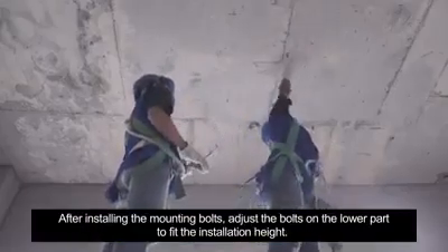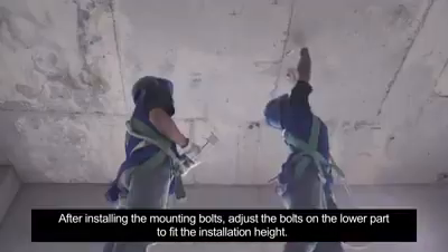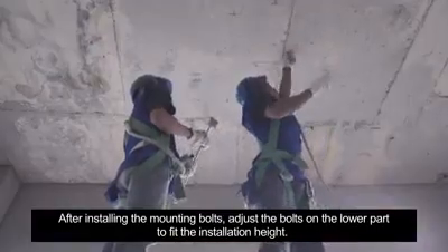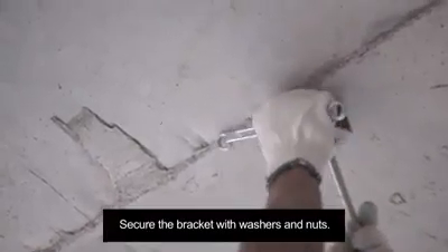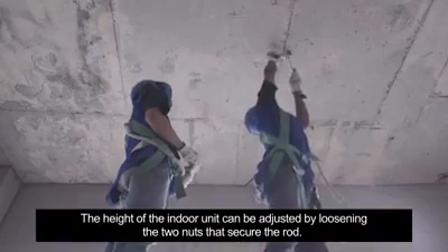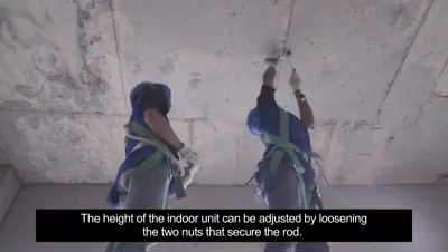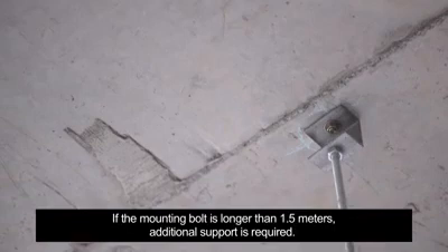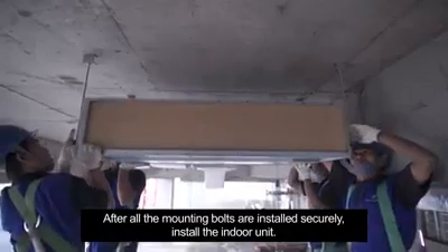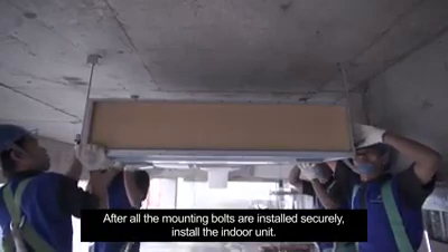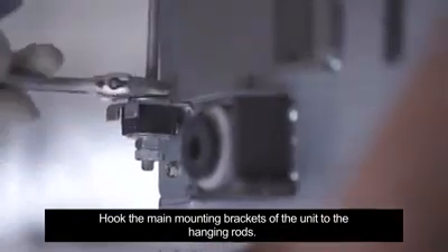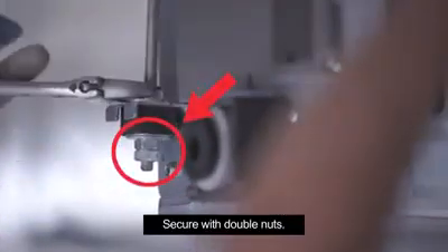After installing the mounting bolts, adjust the bolts on the lower part to fit the installation height. Secure the bracket with washers and nuts. The height of the indoor unit can be adjusted by loosening the two nuts that secure the rod. If the mounting bolt is longer than 1.5 meters, additional support is required. After all mounting bolts are installed securely, install the indoor unit. Hook the main mounting brackets of the unit to the hanging rods. Secure with double nuts.